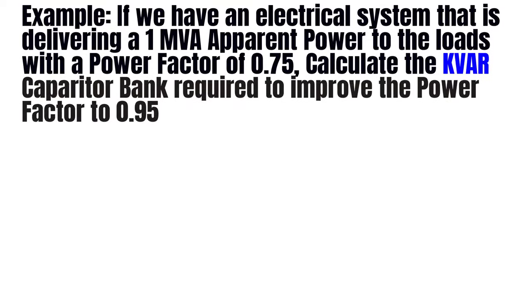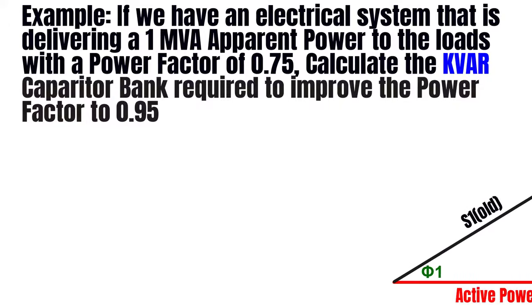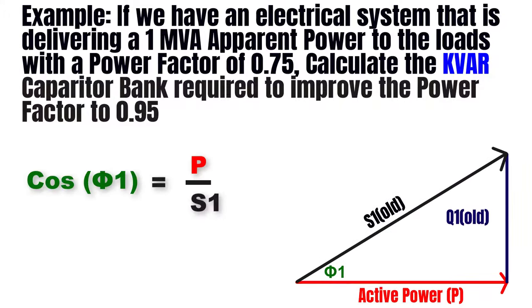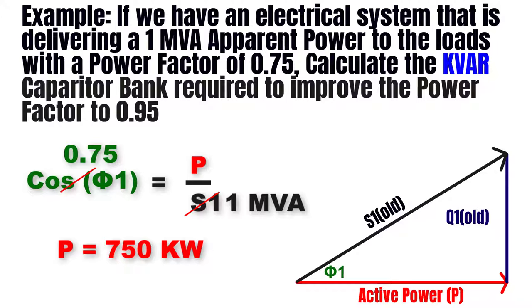Let's take an example. If we have a system delivering 1 mega volt ampere apparent power to the loads with a power factor of 0.75, calculate the kVAR capacitor bank required to improve the power factor to 0.95. For cosine phi 1 equal to 0.75, with S1 equal to 1 MVA, the active power equals 0.75 megawatt or 750 kilowatts.